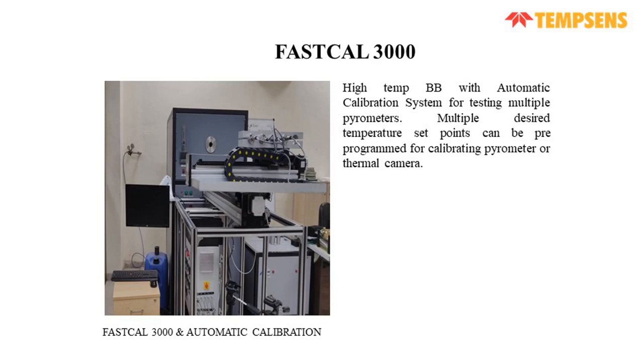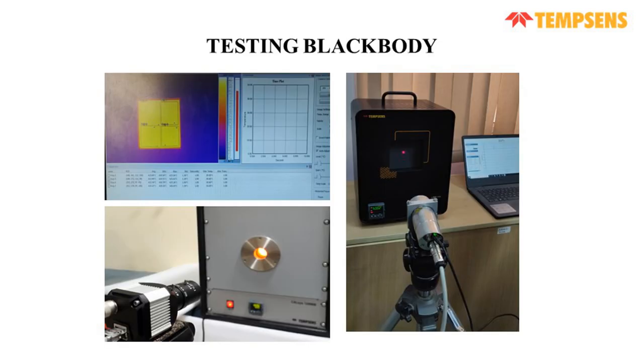We also offer this XY moving system, an automatic calibration system. The pyrometer housing has one master pyrometer and four test pyrometers. It can be customized as per the customer's need, and this can be moved back and forth for the calibration. So this is how the testing of the black body is done with the pyrometers and with the thermal imagers.